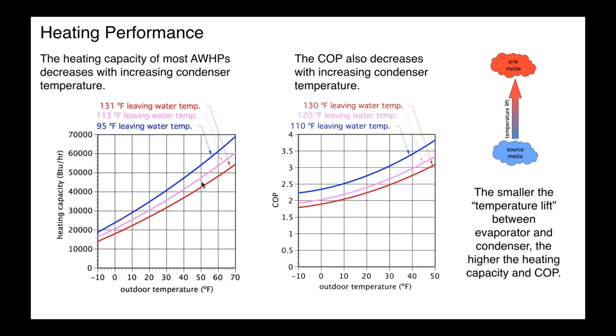Well, the greater that temperature lift is, the lower the heating capacity and the lower the COP the heat pump's going to have. We can't really change the source media temperature. Obviously, we don't have control over that outside temperature, but as designers, we do have control over how hot the water has to be. And the bottom line is very simple. The lower you can keep that water temperature, the better that heat pump is going to perform.